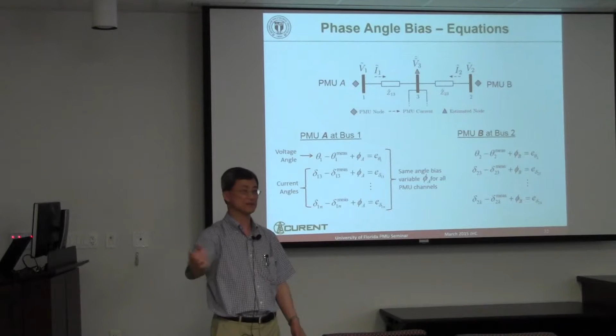So the idea is actually very simple. For every PMU with this kind of connection, you introduce a phase shift at all the channels, because that's how the phases are computed. Remember, a phasor has a magnitude and a phase. The phase is natively computed in the PMU and should be accurate even if the magnitude is scaled improperly—whether amplitude is high or low, the phase stays the same. So you can do all this correction.